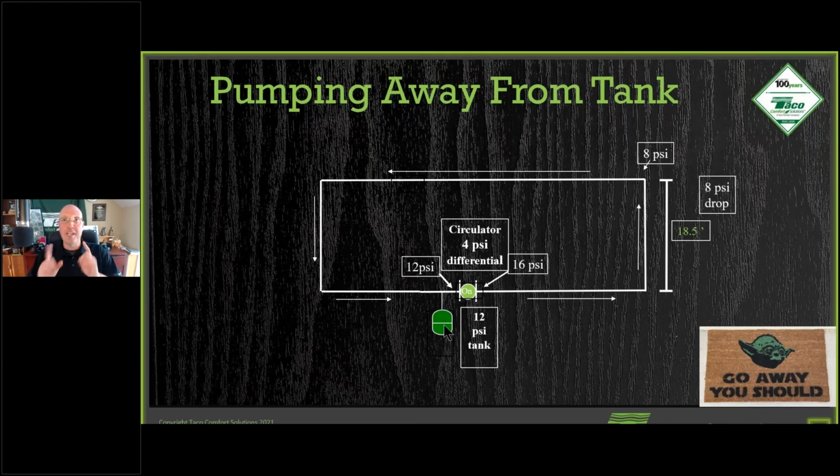Remember, one thing: you can't pump into the expansion tank, because this is a set volume of water sitting in here. If I pump water into the expansion tank and expand the bladder, what's behind it? You took water out. I can't put air in, right? Because there's no way for the air to get in here. All right. I can't have vacuum because it's a 1/25th horsepower circulator.